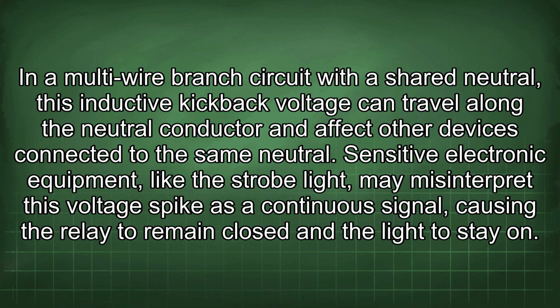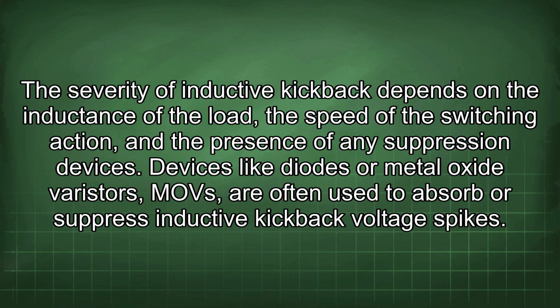In a multi-wire branch circuit with a shared neutral, this inductive kickback voltage can travel along the neutral conductor and affect other devices connected to the same neutral. Sensitive electronic equipment, like the strobe light, may misinterpret this voltage spike as a continuous signal, causing the relay to remain closed and the light to stay on. The severity of inductive kickback depends on the inductance of the load, the speed of the switching action, and the presence of any suppression devices. Devices like diodes or metal oxide varistors, MOVs, are often used to absorb or suppress inductive kickback voltage spikes.